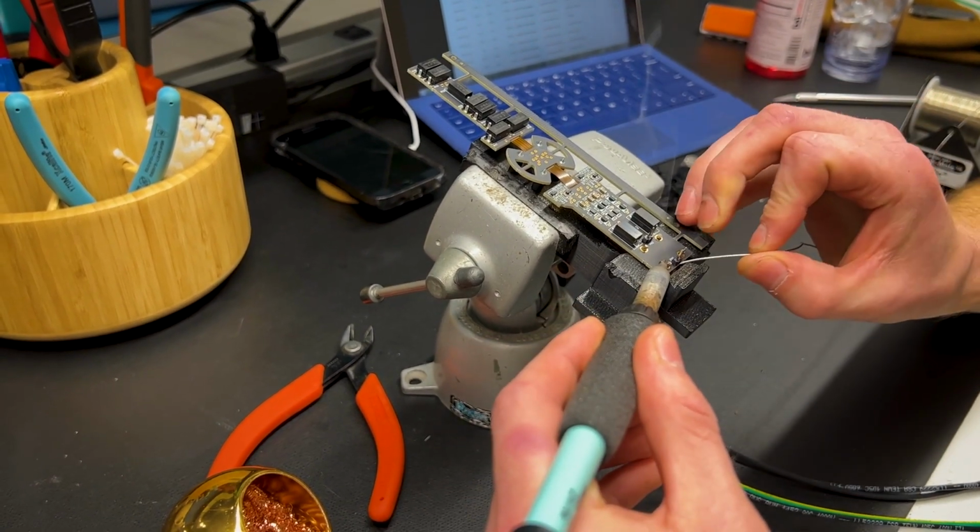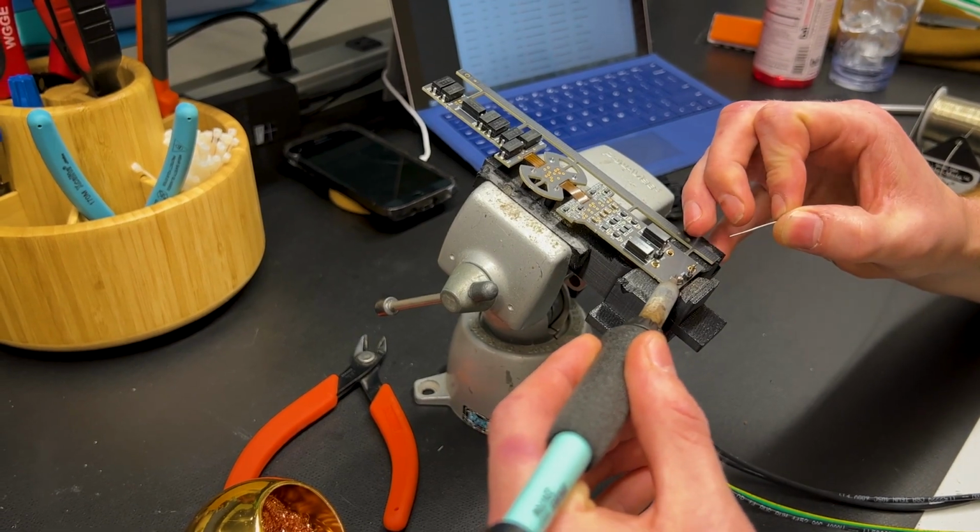Can you tell us a little more about the design, specifically the faceplate, what the symbols mean, and how the LEDs visually present when voltage is present? Sure. When you look at the faceplate of the check volt, you'll see 3 red lines and a green line. As this is hooked up to the bus, you'll have a line for each phase: line 1, line 2, line 3, and then a ground. When this is in use, the 3 lights will be lit and the ground light will be off. The ground light comes on when you lose a phase in one of the lines.